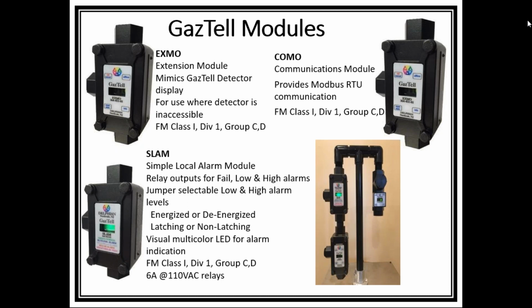And the relays in the SLAM are rated at 6 amps, which is pretty much hefty enough to do most jobs. The only time I recommend going to an auxiliary relay is when you have maybe some fans or motors that are running at greater than 6 amps, maybe a 10 amp ventilator. In that case, you'd want to use an auxiliary relay to do the job and allow the SLAM to energize that auxiliary relay. The COMO is used when you have applications where you want to talk to a PLC using Modbus RTU communication. And this actually allows an addressable location to a sensor. So when you attach a COMO to a detector head, it now is addressable and then can be put onto a PLC of your desire, or a DCS system, or anything else that requires addressable communication.